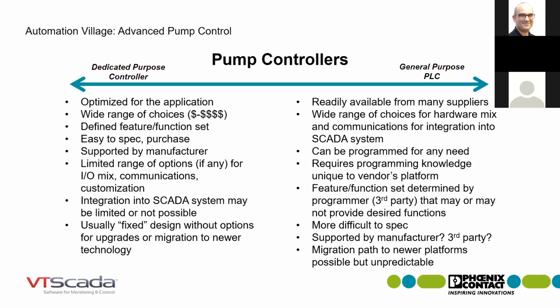However, there are some challenges on this side of the spectrum. If you're going to be programming a PLC, that usually requires knowledge unique to the vendor's platform, and that can vary even from one vendor's platform to the next. As Dave mentioned earlier, there is a standard programming environment, IEC 61131, which has brought some consistency to programming for a wide range of PLCs on the marketplace. In fact, our PLCnext can be programmed using 61131 as one of the basic options. But still, even within any manufacturer's specific environment, there are things you have to know about their hardware and their ecosystem.